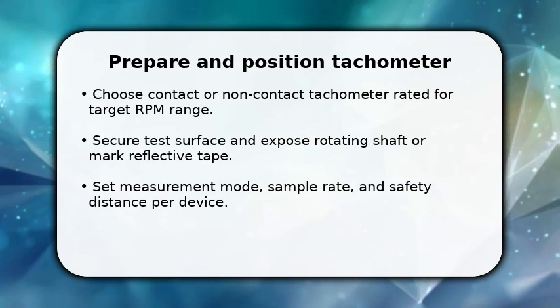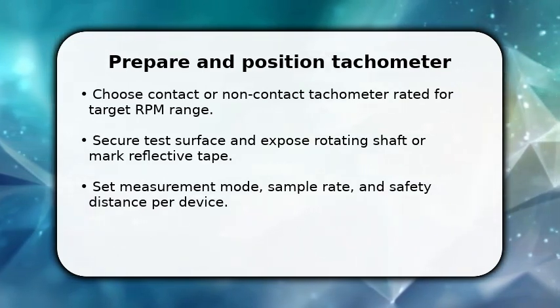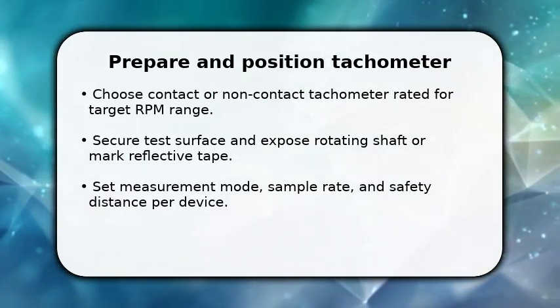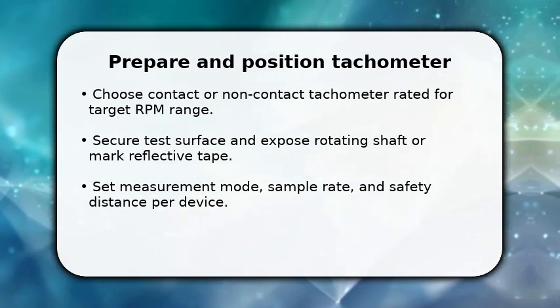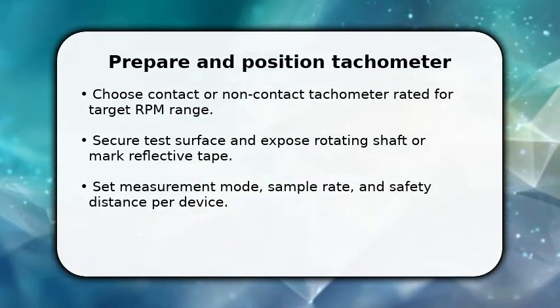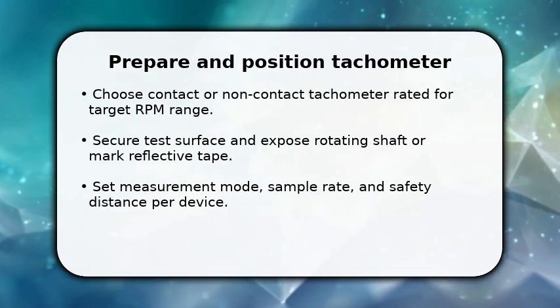You start by selecting the correct tachometer type for the shaft. Contact for slow, non-contact for high speed. Attach reflective tape if using optical sensing. If contact, align the probe cleanly on the shaft.